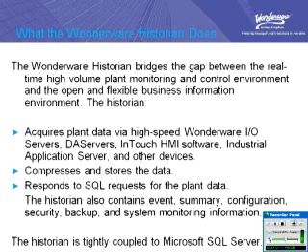Now, because the historian is tightly coupled with Microsoft SQL Server, then it can make the data available to any tool that is capable of executing an SQL request. So immediately the data is available to a whole variety of mechanisms. In addition to storing the plant data, it also contains event summary configuration data and security backup and system monitoring information.